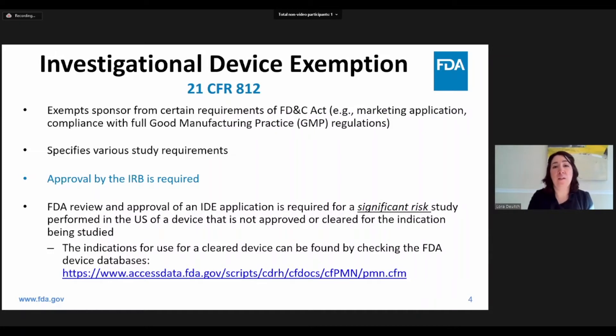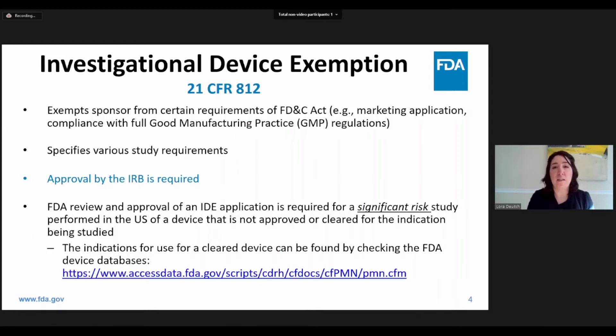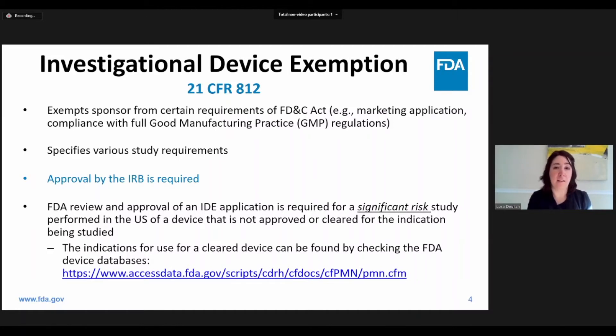When determining if your clinical trial is subject to the IDE regulations, the first thing to consider is what the device is cleared or approved for by the FDA — in other words, what does the testing of the device support? This is reflected by the indications for use of the device, which gives specifics about what the device is meant to diagnose or treat and may specify a patient population if there are restrictions. The device's indications for use can be found by checking the FDA's device databases.